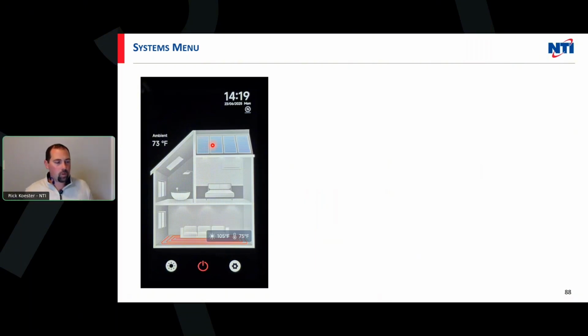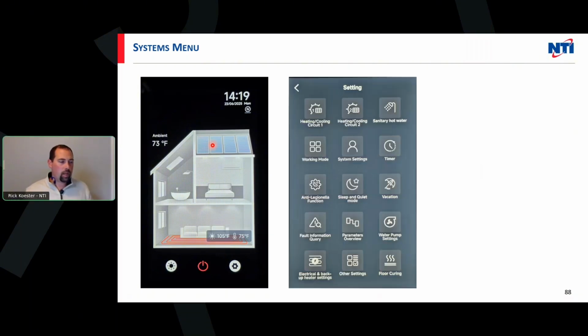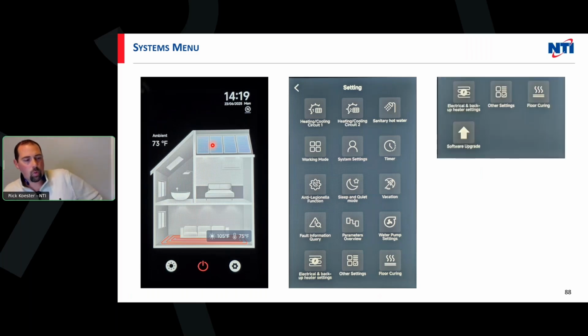All right, so first things first, at the bottom right of the main screen there's a little setting button. It brings up this screen, and if they scroll down, that's the extension of it, where there are a lot of different options. We have the ability to get into our heating and cooling circuits, domestic hot water under sanitary hot water, and working mode. This is where we really tell the machine what we need it to do. There's also system settings, timer, and a bunch of other stuff, and we're going to go through probably the most important ones today.